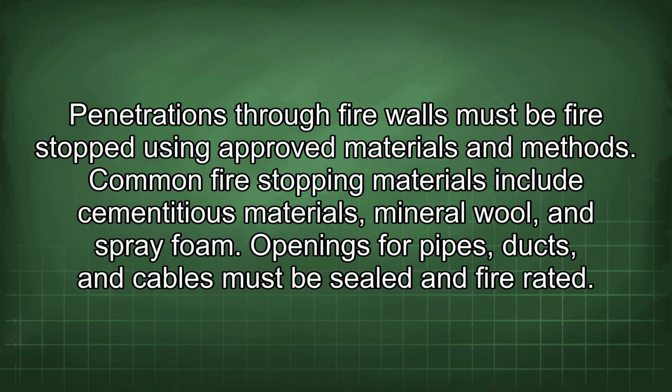Penetrations through firewalls must be fire-stopped using approved materials and methods. Common fire-stopping materials include cementitious materials, mineral wool, and spray foam. Openings for pipes, ducts, and cables must be sealed and fire-rated.